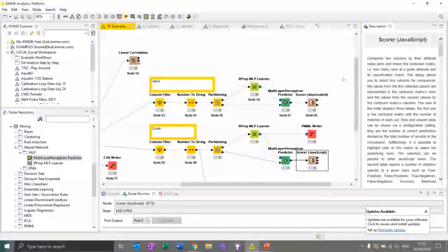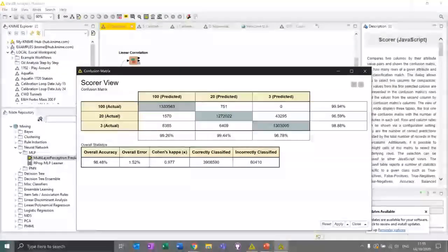The results in the confusion matrix of this exercise of training the neural network are quite positive. I have three cooler conditions: 100% okay, going towards failure, and failure is imminent. These are the three numerical values represented here. In this confusion matrix, we see the actual scoring of the classes that were provided to the neural network in this case, on the unseen data.